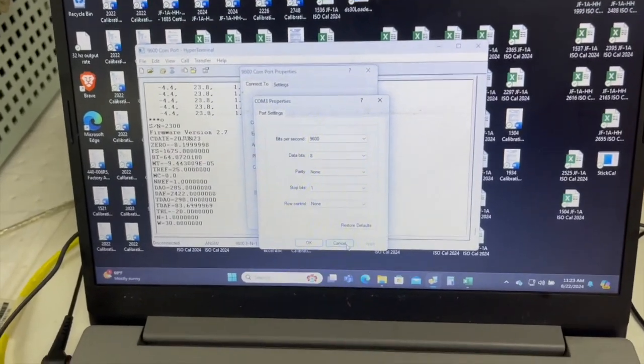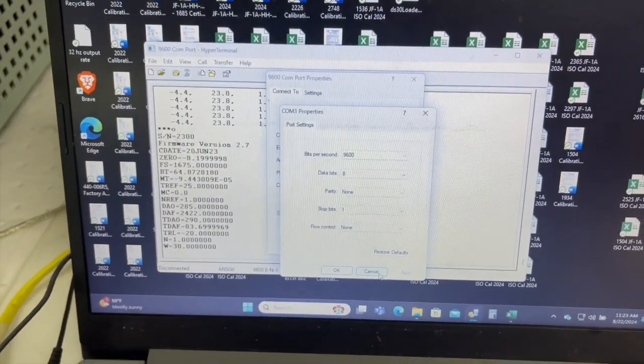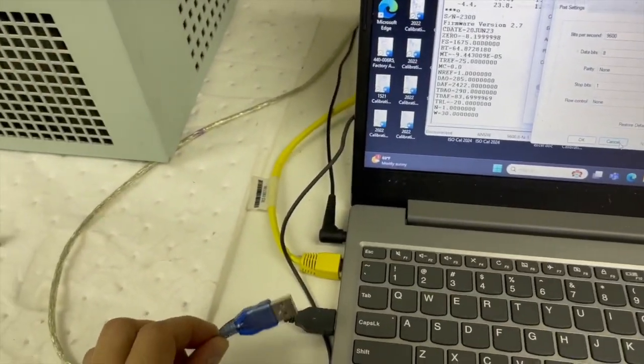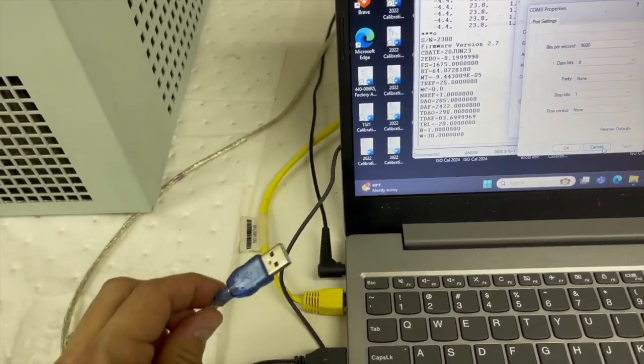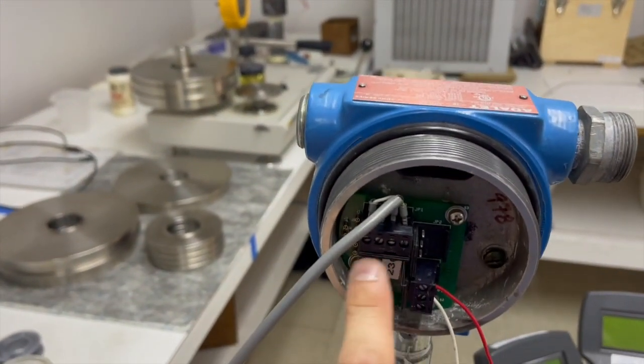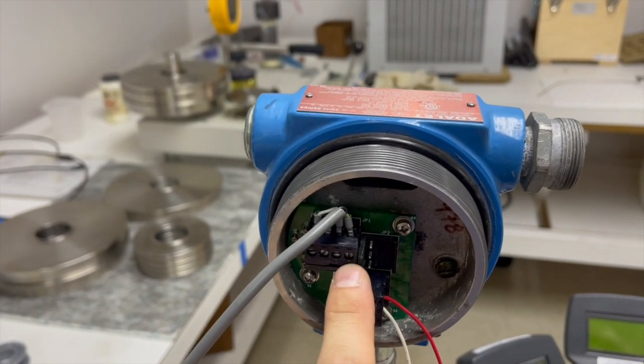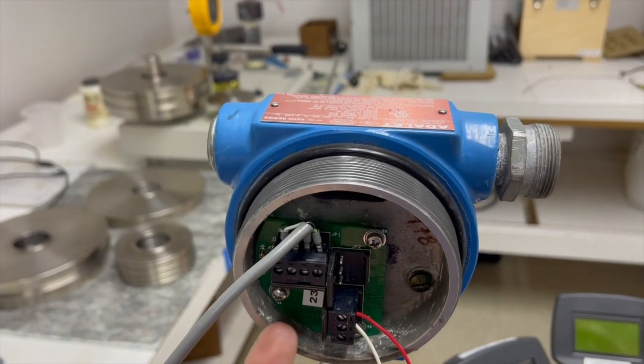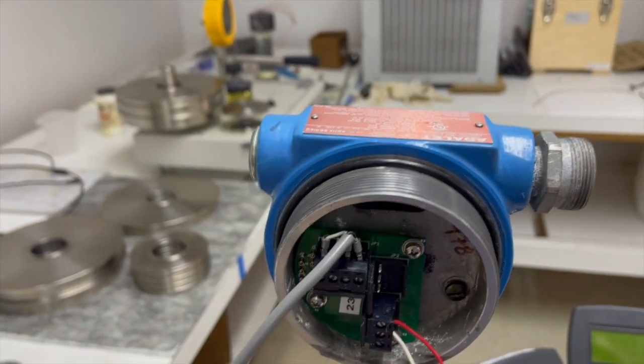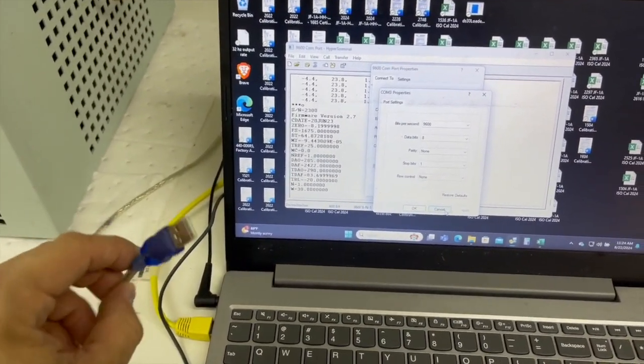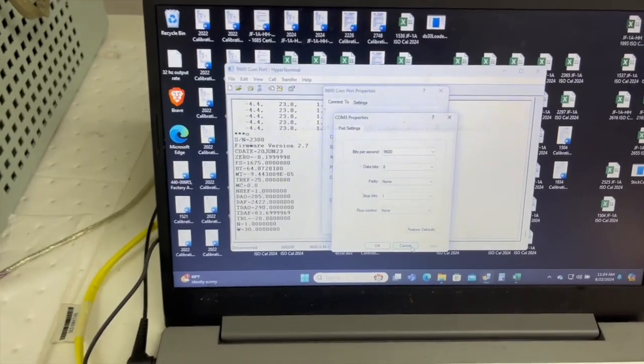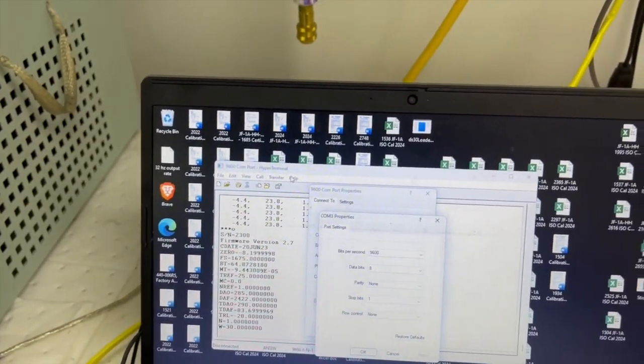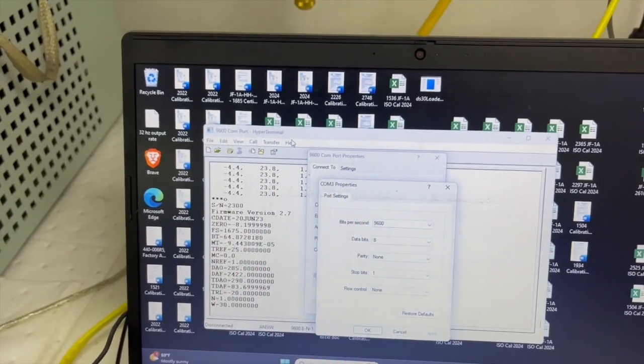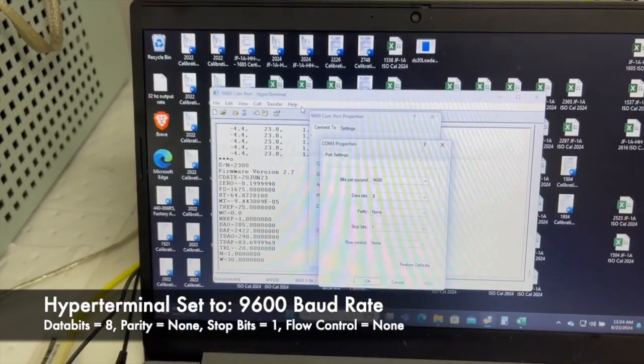So when you first fire up hyperterminal, you want to create a connection, and what you'll do is you'll connect the sensor with the JF-1A test cable we'll give you, which is a USB to serial port test cable that you connect here at the 4-pin header on your JF-1A sensor, which can either be the black version like this or the green version that connects underneath. It'll come with the appropriate connection. Okay, and over here it connects into your USB terminal. Then you open up Hyper Terminal, which is a free program you can download for Windows. It just connects via the terminal program.